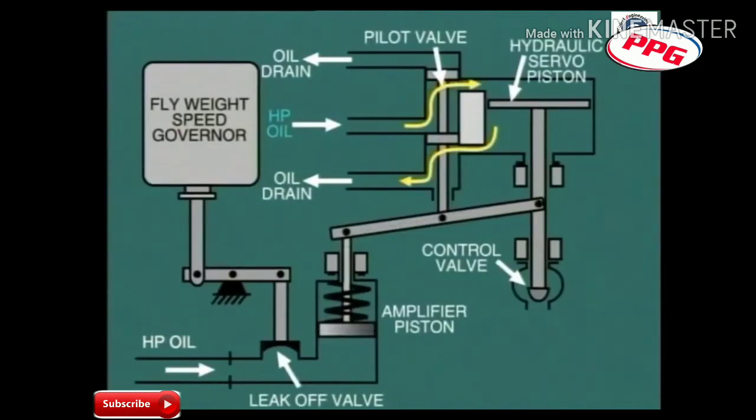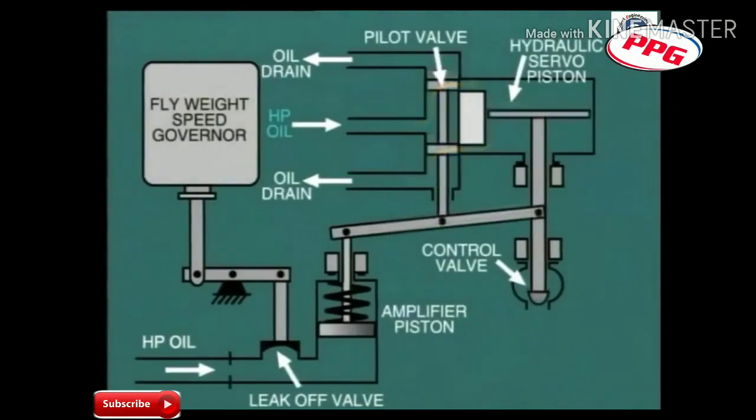At the same time, the pilot valve exposes the space below the piston to the oil drain and returns the oil to the tank. The high-pressure oil above the piston pushes it downward and consequently moves the control valve in the closed direction.